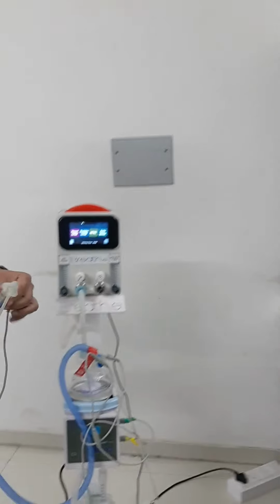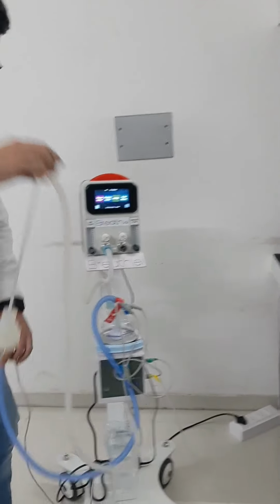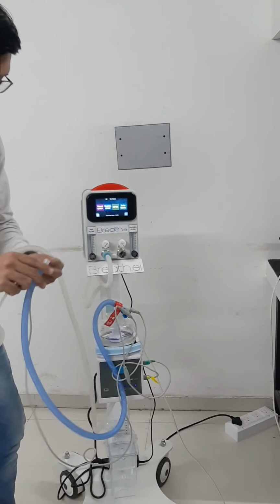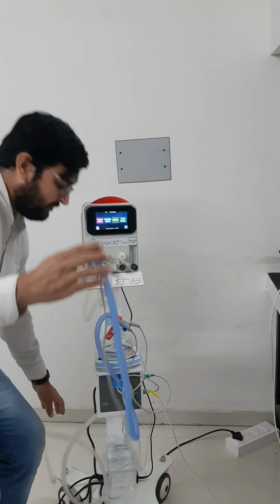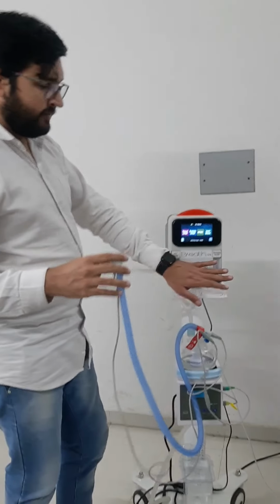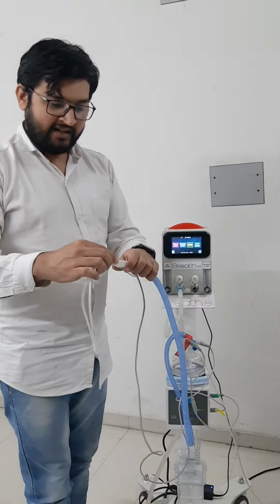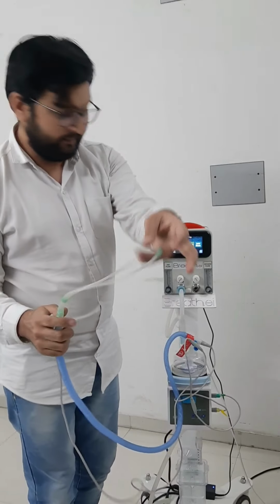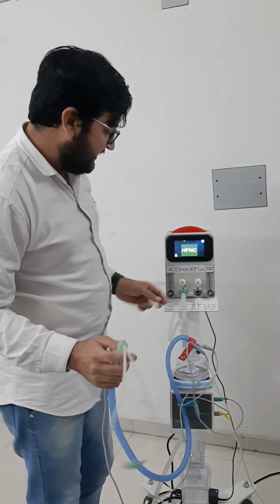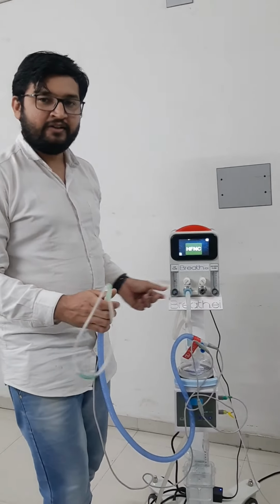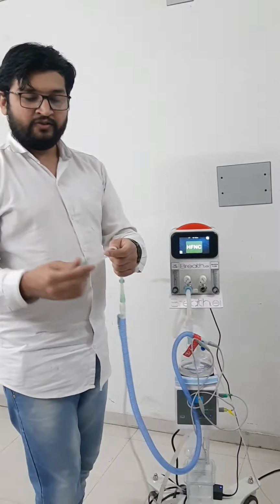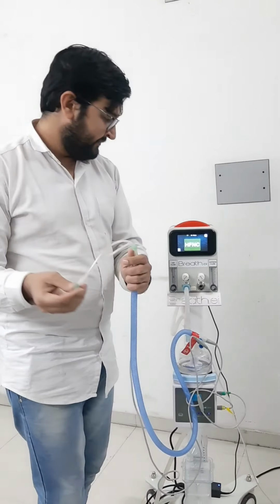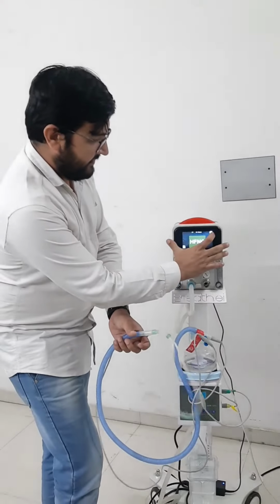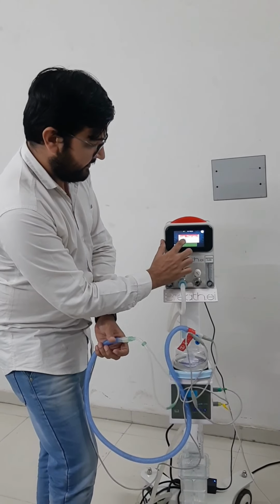The third mode is HFNC. In HFNC mode, you don't have to connect any expiratory limb to the machine or any other part. You just simply connect the HFNC cannula to the circuit at the inspiratory limb, start the HFNC mode and set the required flow according to FiO2. It gives continuous flow to the patient. To stop, just click on this stop button and confirm.